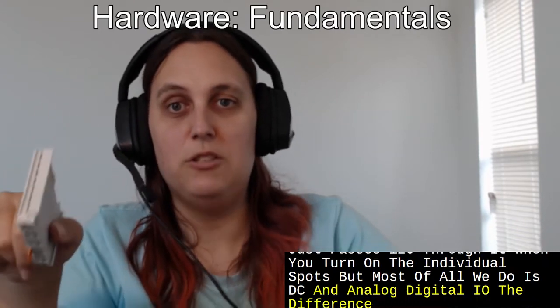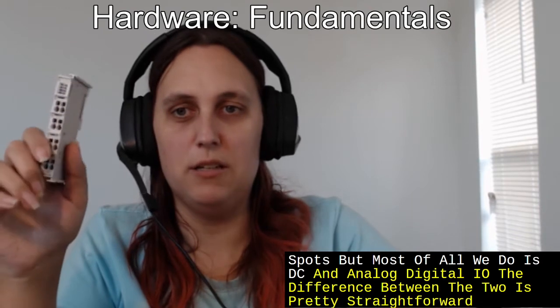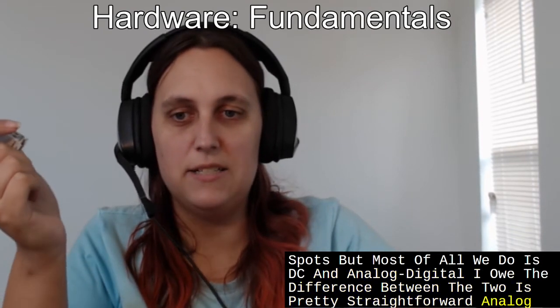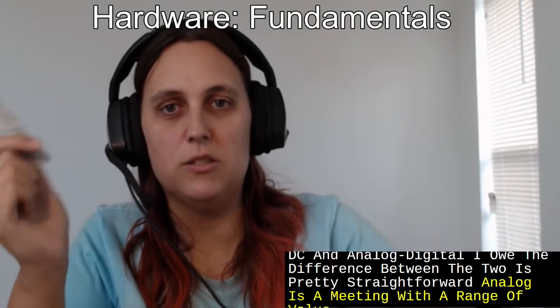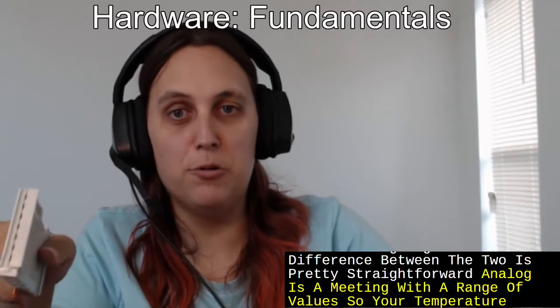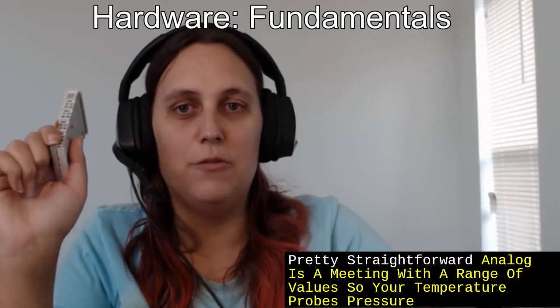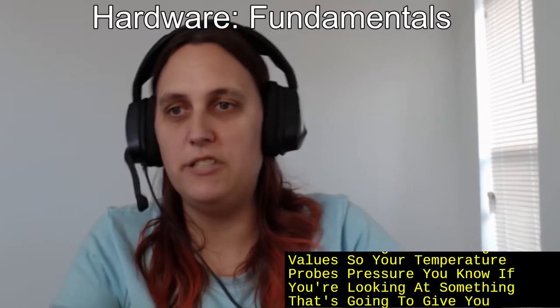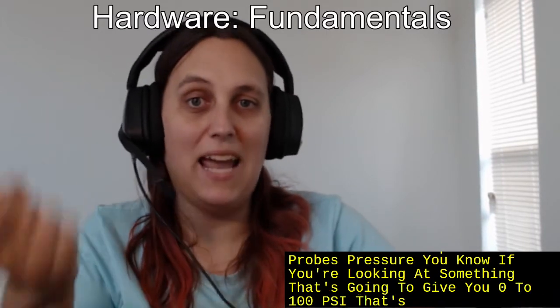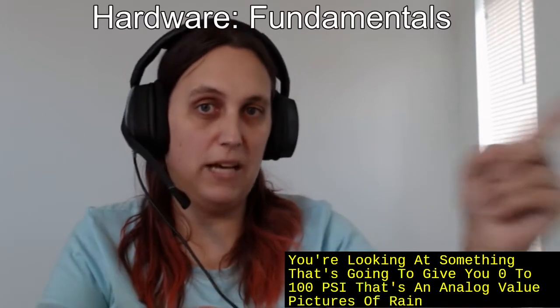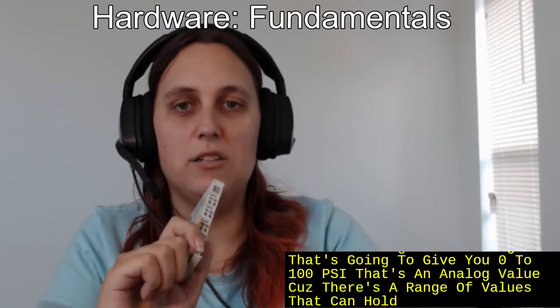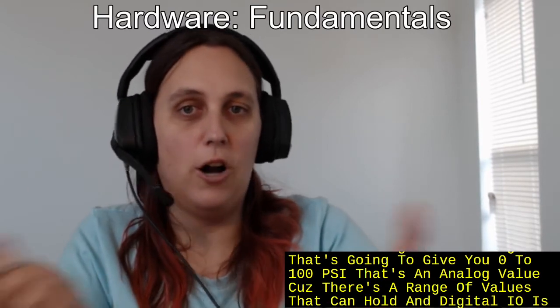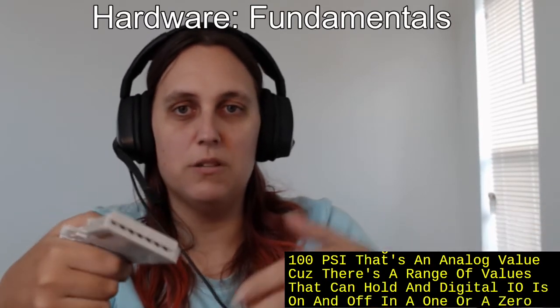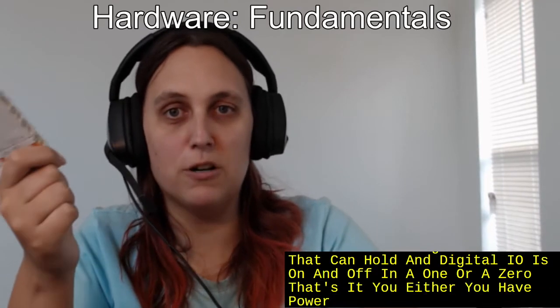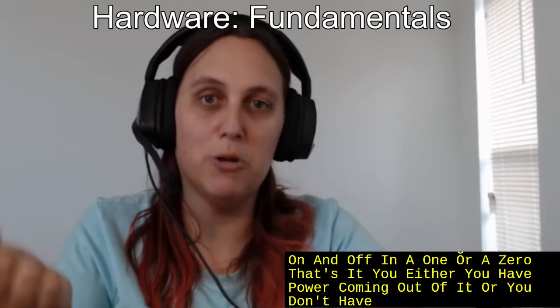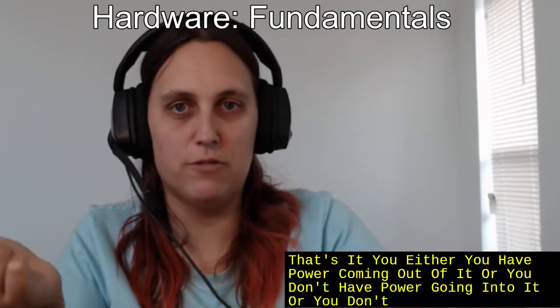The difference between analog and digital is straightforward. Analog is anything with a range of values, like temperature probes or pressure - if you're looking at something that gives you 0 to 100 psi, that's an analog value because there's a range it can hold. Digital IO is on and off, a 1 or a 0. That's it - you have power coming out of it or you don't, power going into it or you don't. Digital versus analog.